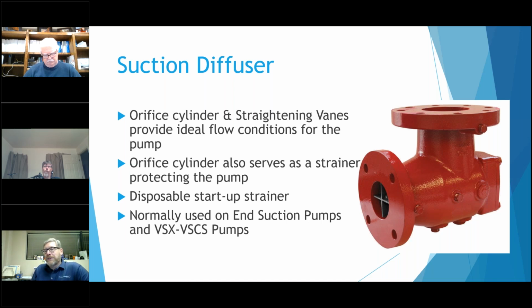I do want to point out there's a disposable startup strainer that comes in these. It's a fine mesh strainer. It's in there to get some of the fine particulate out of the system. So you run the system a little bit, and you're careful on opening up the back of that because there is a rubber O-ring. If you pull it open too quickly or too hard, you can actually stretch the O-ring and it won't go back into its seat.